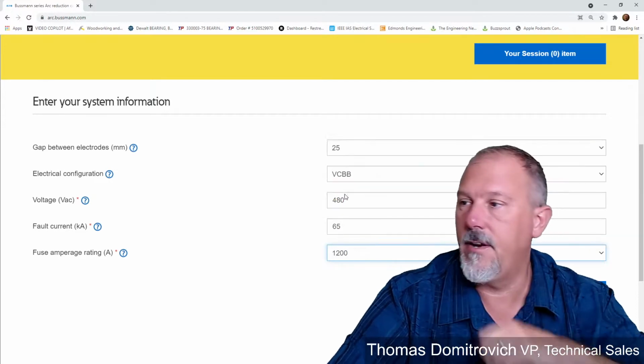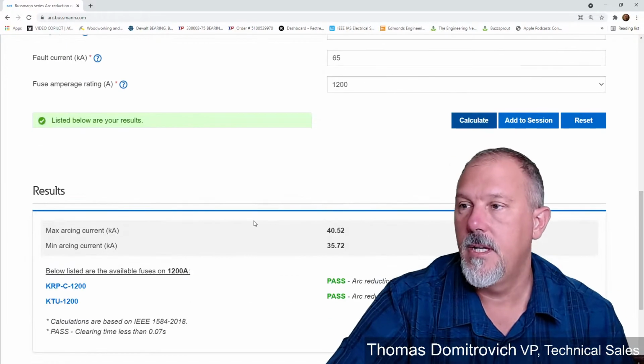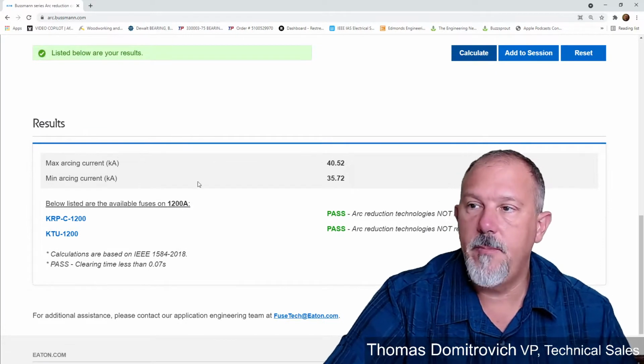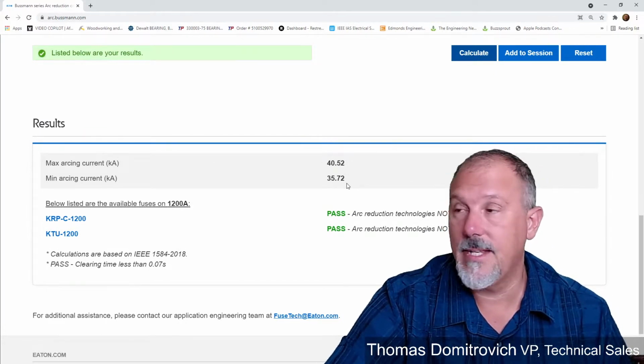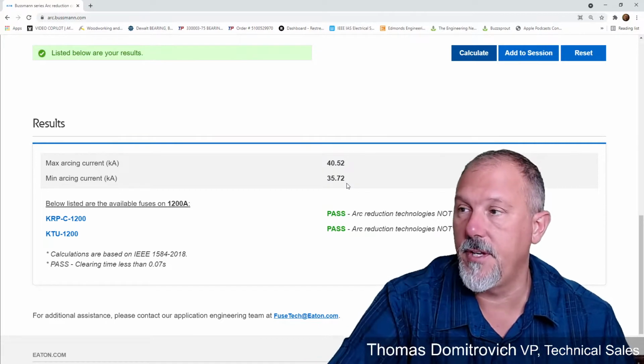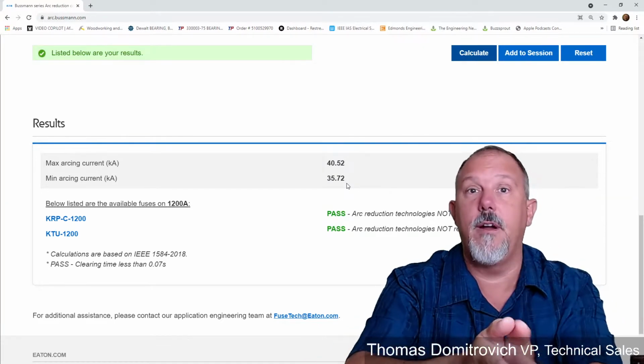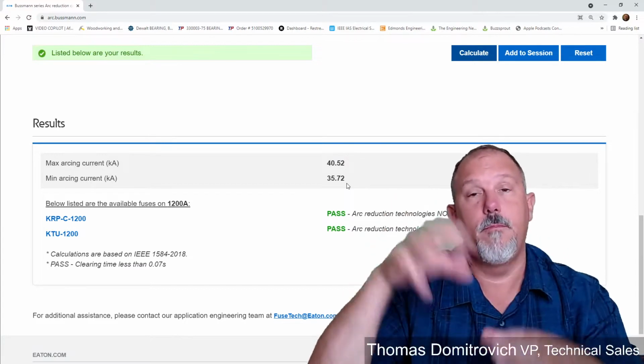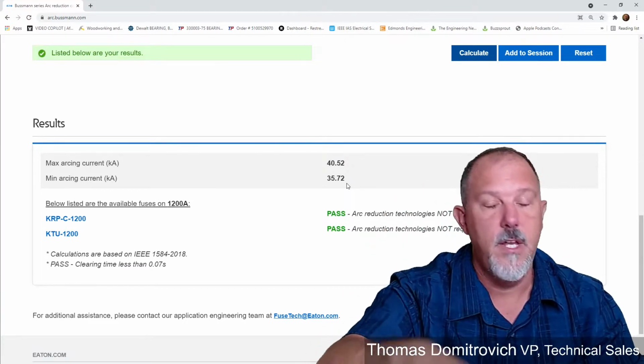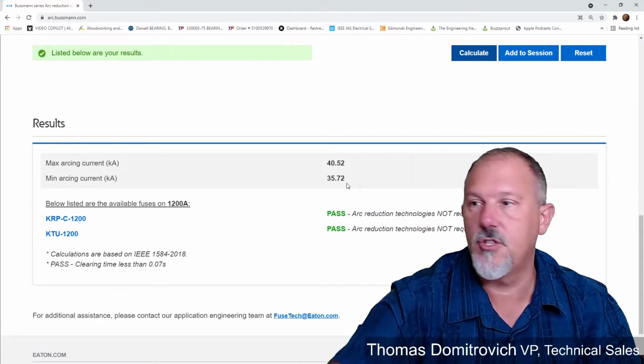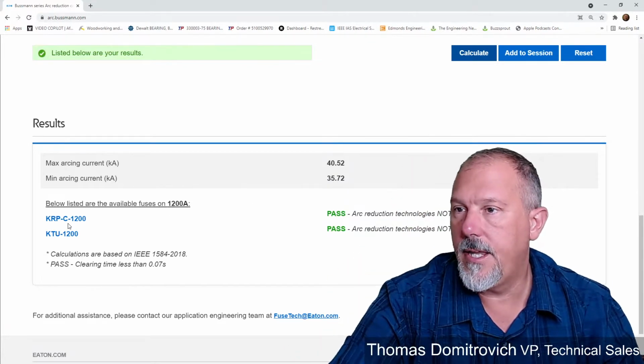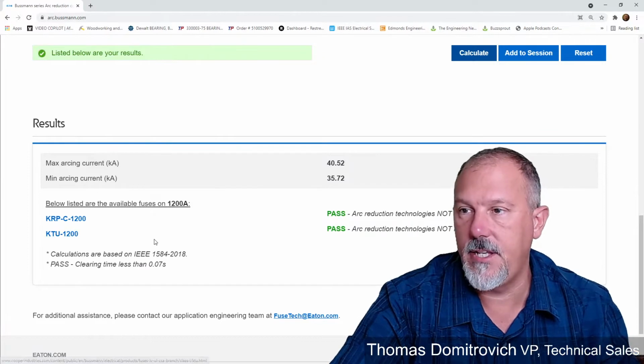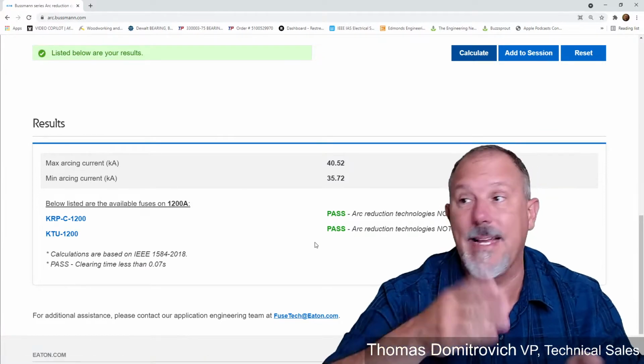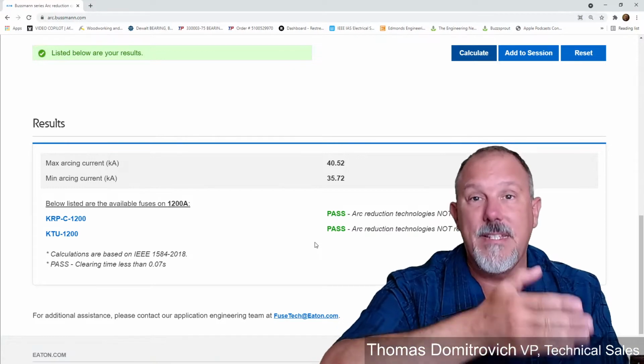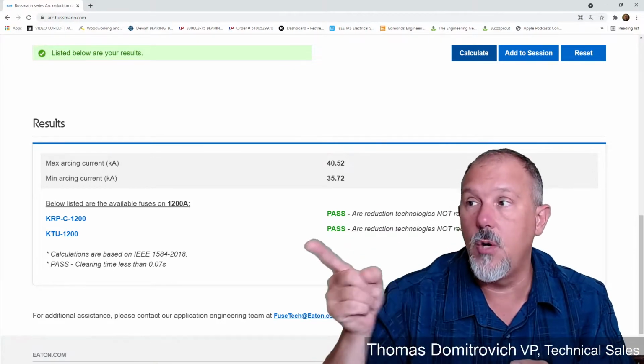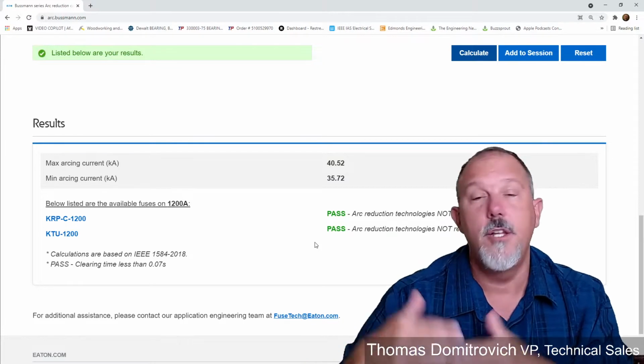You calculate, and it tells you what your maximum and minimum arcing currents are coming from the utility at that service, or from upstream. Based upon the fault current that you put in, you would have to figure out your minimum fault current, the fault current that does not have the motor contribution from upstream. KRPC 1200 passes and KTU 1200 passes, so you don't need arc reduction. That tells you that you have a clearing time of 0.07 seconds or faster at the lowest arcing current. We picked the lowest arcing current to do that evaluation.